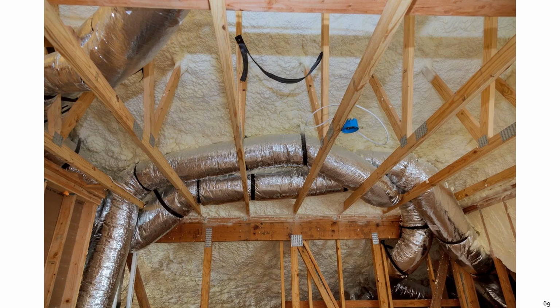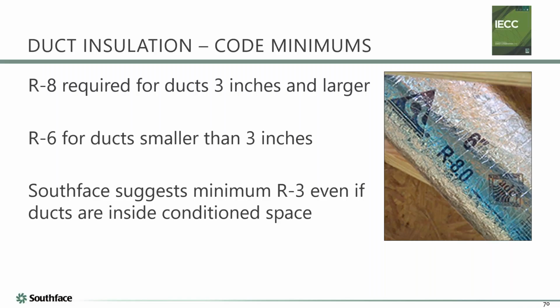So what I wanted to say here is that, if you get your ductwork inside the conditioned envelope, which it is in this case here, don't forget the fundamentals. Don't just think, oh, well, it's in the conditioned space, it doesn't matter. I'm not going to worry about sealing, and I'm not going to worry about hanging it properly. These pinches and things, they don't really matter, because obviously the rooms aren't going to get the preferred CFM numbers if you have these pinches and these tight twists and turns like you see here. So definitely not a good example of a good system here.